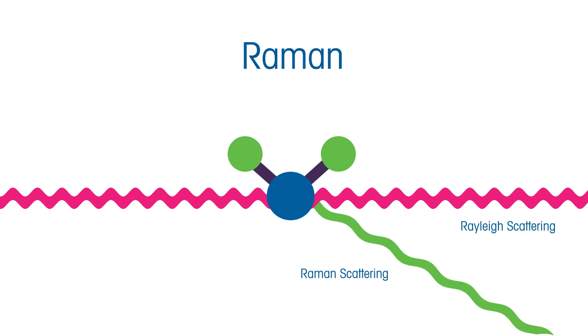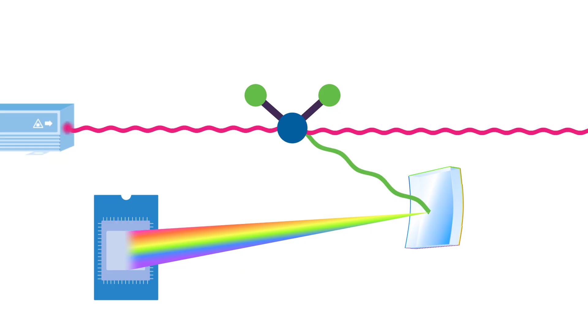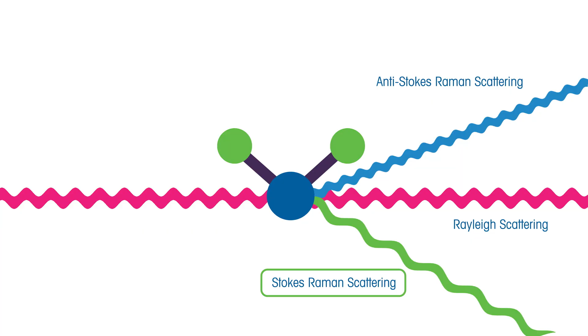Despite the effect being weak, today's technology advancements in solid-state lasers, gratings, and CCD detectors make Raman a valuable tool for identifying and monitoring compounds in a reaction or crystallization. The scattering can be either Stokes-Raman scattering, where scattered photons are at lower frequencies than the excitation photons, or anti-Stokes scattering, where frequencies are higher than those of the excitation photons. Stokes scattering is the most common type of inelastic Raman scattering that is measured by Raman instruments today.